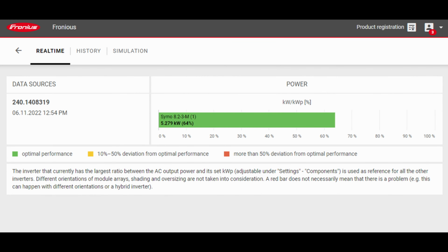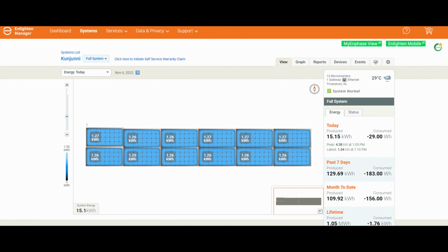In certain inverters like Fronius, we can also monitor the performance ratio. So performance ratio is the key performance indicator. It's a KPI which should be analyzed for solar power plants. How is the performance of the plant? So what is the PR? This is how we analyze, right? So if the PR is more than 80 or 90 percent in the residential sector, that is, the plant is performing excellent, right?